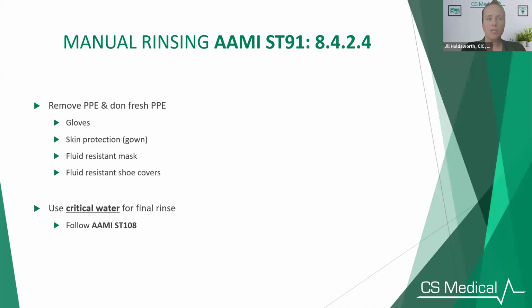And I did see a comment just now about there are some newer things in the endoscopy departments that only have IFUs for manually soaking, and I understand that, and it's an IP's nightmare that we're still seeing things that are only allowed to be manually high-level disinfected, but let's focus on probes for now. So again, that critical water could be critical, and if you have it or not, if the IFUs are calling for it and you don't have it, then that's something that's going to need to be discussed with your leadership. Next slide.